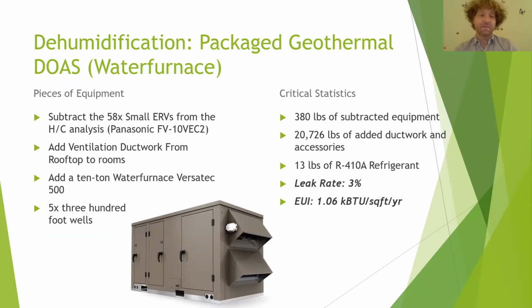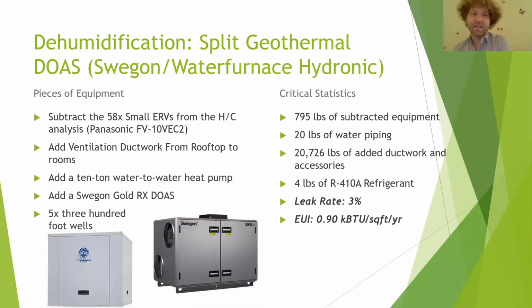The third system is a geothermal system, packaged geothermal. This has a lot of the benefits of the first system, and it's for plugging into it—if you're already using geothermal for heating and cooling, you can use it for dehumidification too. There's also another variation where you split it apart: you use a really high performance ERV, then use the geothermal water-to-water unit. These systems perform really well.